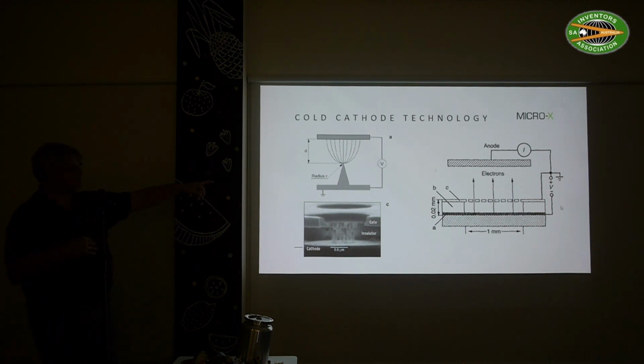The beauty of this is that, as opposed to a heated element, you can't turn on a heated element very quickly. You can turn it on and you see it glow up, and when you turn it off, you see it glow down. It actually goes at a speed that you visually see. We can turn these things on in microseconds, so we can do really fast pulsing of X-rays, which you wouldn't otherwise be able to do. And that's a unique feature that we're trying to utilize in some of our products.